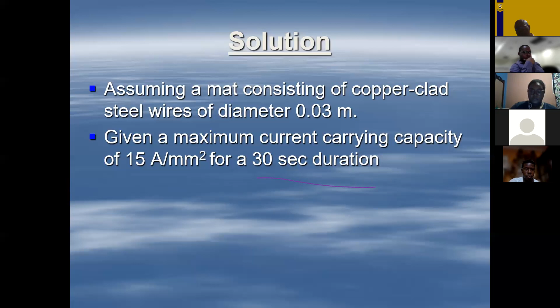If these can carry up to 15 amps per square millimeter for 30 seconds, then if it can carry the maximum current, we're good. The mat won't be converted into a fuse under fault. Because if the current carrying capacity of the material used to design the mat is too low, then it's just going to melt. All right? So these are some of the things that I'm saying. We're making assumptions, but you would have this information.